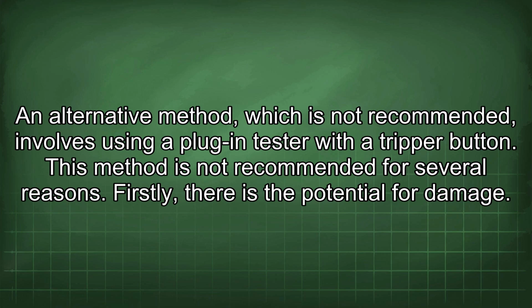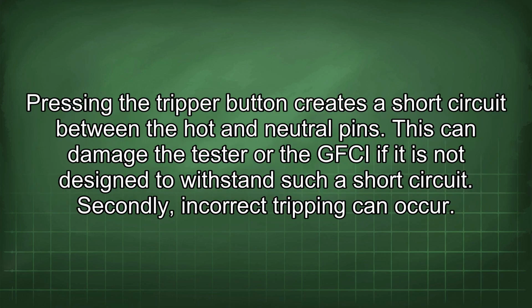An alternative method, which is not recommended, involves using a plug-in tester with a tripper button. This method is not recommended for several reasons. Firstly, there is the potential for damage. Pressing the tripper button creates a short circuit between the hot and neutral pins. This can damage the tester or the GFCI if it is not designed to withstand such a short circuit.